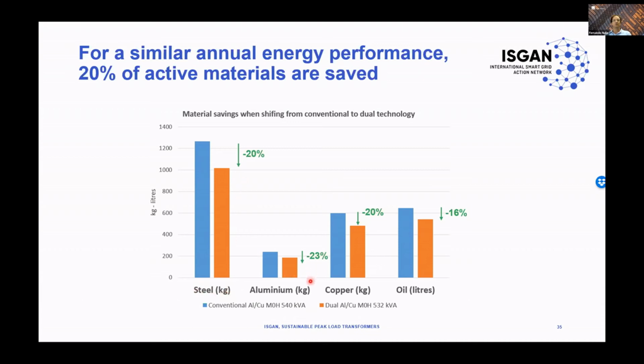We have used a design which has an aluminum coil and a copper coil, so for low voltage and high voltage. The reduction in these two materials is around 20% as well. And the need for oil is reduced by 16%. So overall, the advantage is that for the same energy performance and the same peak capacity, less material is used.